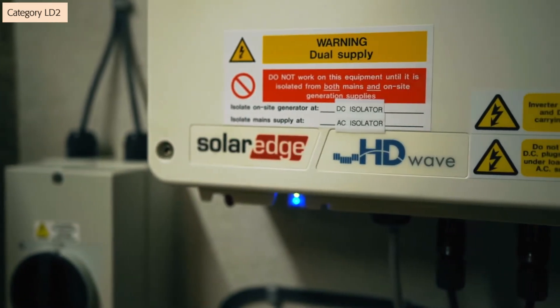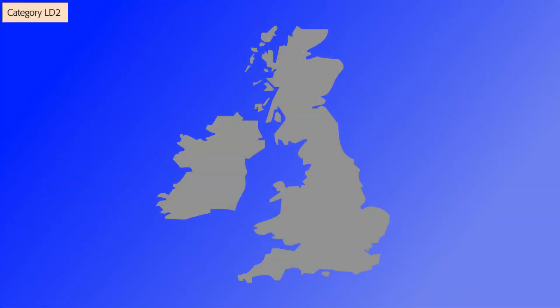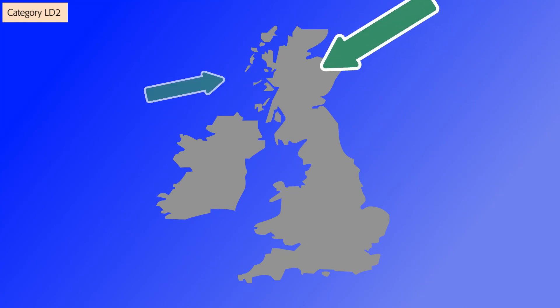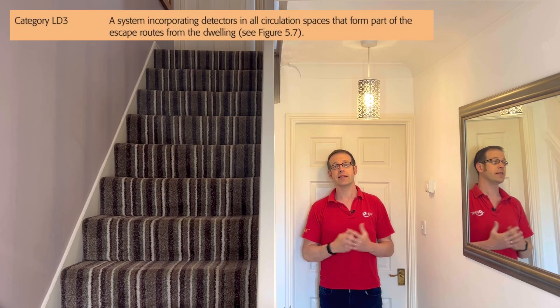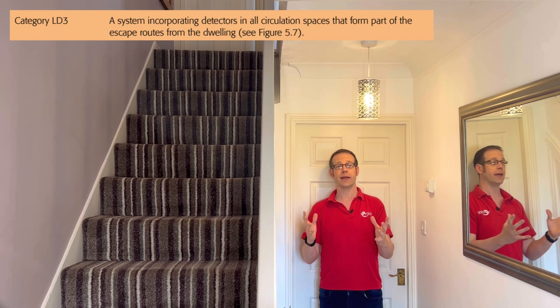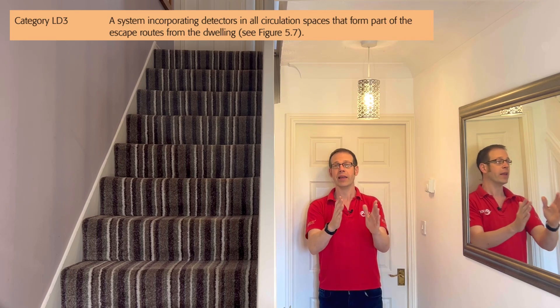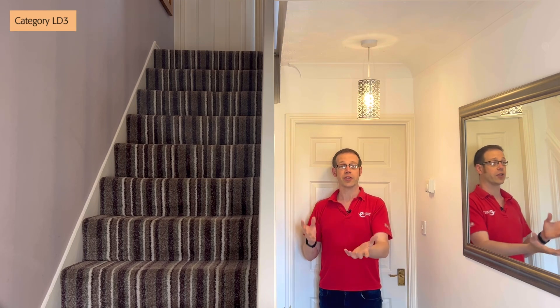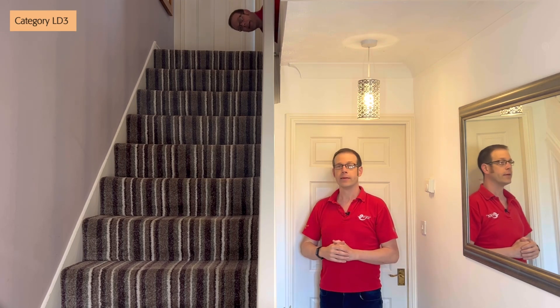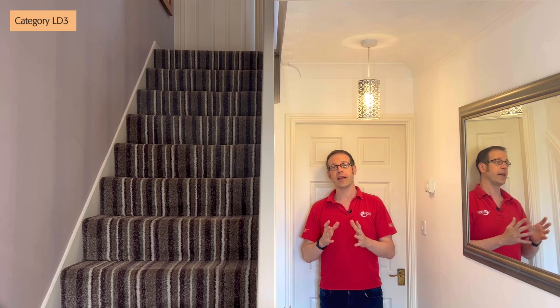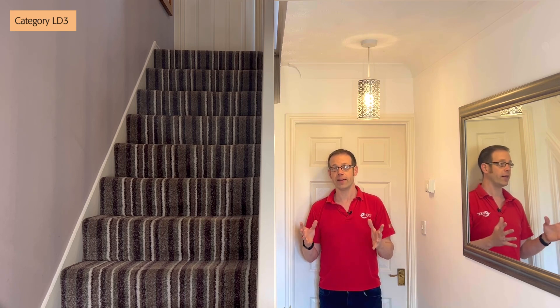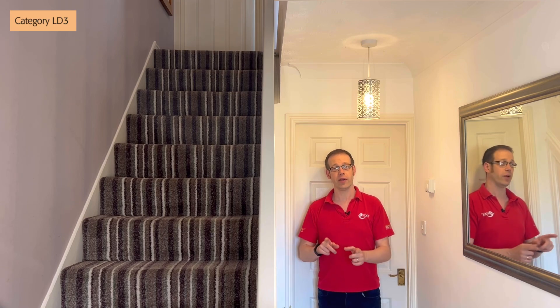The same guidance goes for lofts as with an LD1 system — if it has an inverter or similar for a PV system then it should have smoke alarms installed. It's worth noting that in Scotland and Northern Ireland, LD2 is the starting point for all new builds and may need to be higher in certain circumstances. In England and Wales the starting point for all new builds is category LD3, which is a system incorporating detectors only in all circulation spaces that form part of the escape route from the dwelling. So in our example home you would only need to install detection in the hallway and landing to cover the escape routes — no other room would require one. This is purely to alert people that their route out of the building is under threat from a fire.